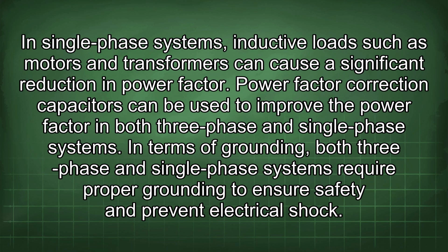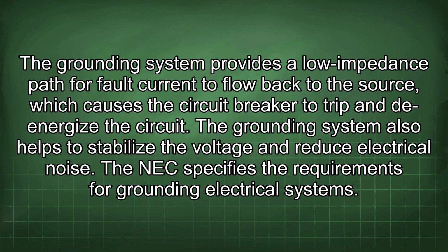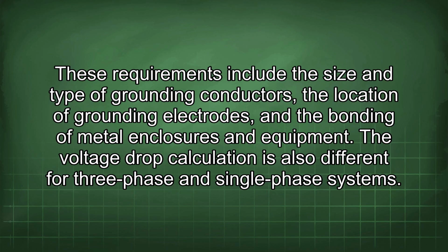In terms of grounding, both three-phase and single-phase systems require proper grounding to ensure safety and prevent electrical shock. The grounding system provides a low impedance path for fault current to flow back to the source, which causes the circuit breaker to trip and de-energize the circuit. The grounding system also helps to stabilize the voltage and reduce electrical noise. The NEC specifies the requirements for grounding electrical systems. These requirements include the size and type of grounding conductors, the location of grounding electrodes, and the bonding of metal enclosures and equipment.